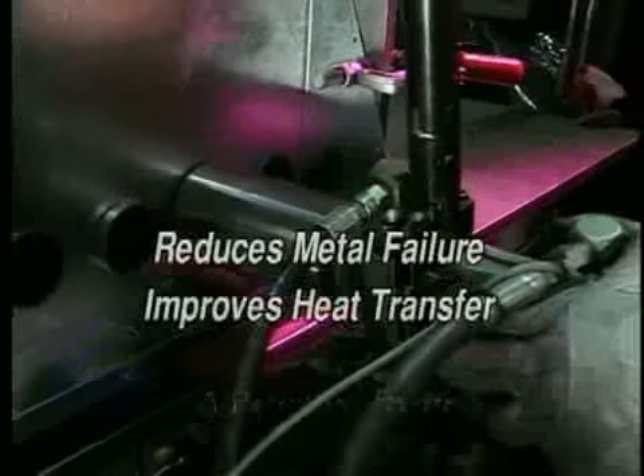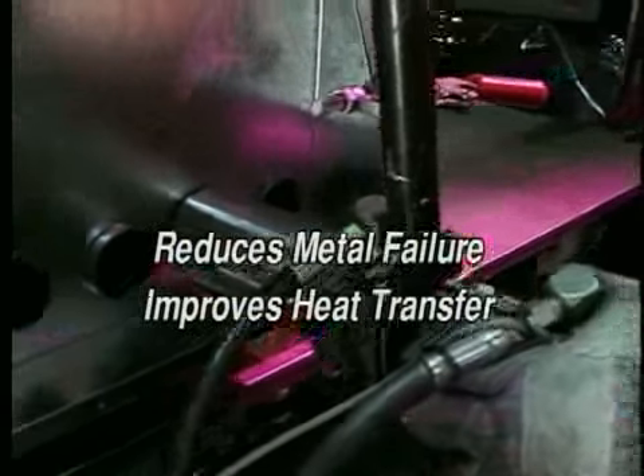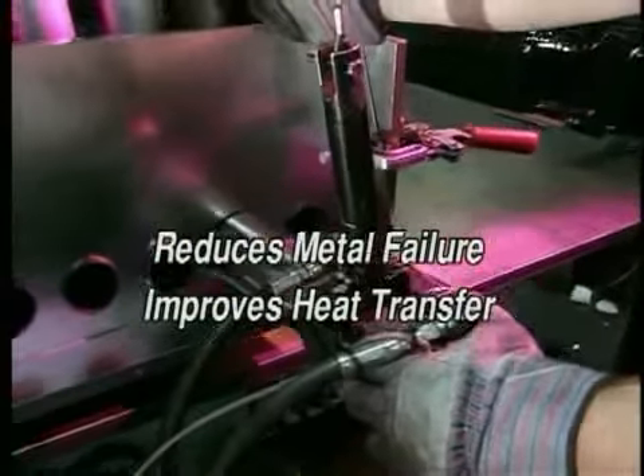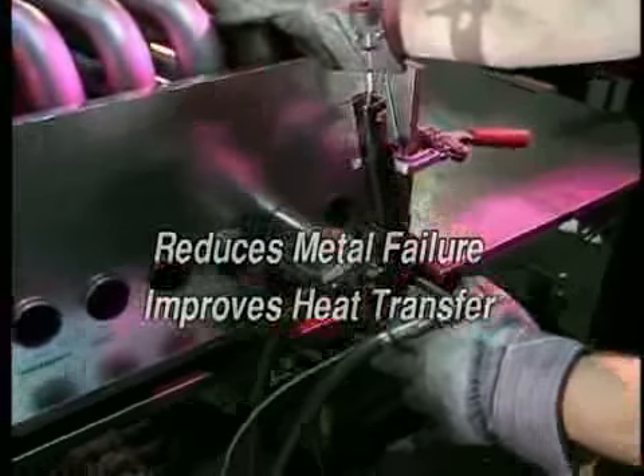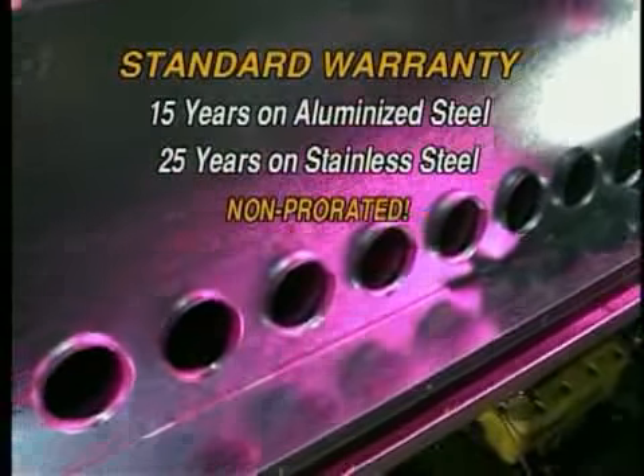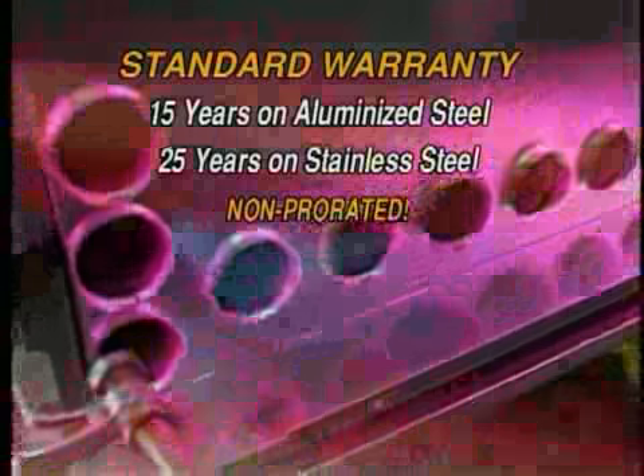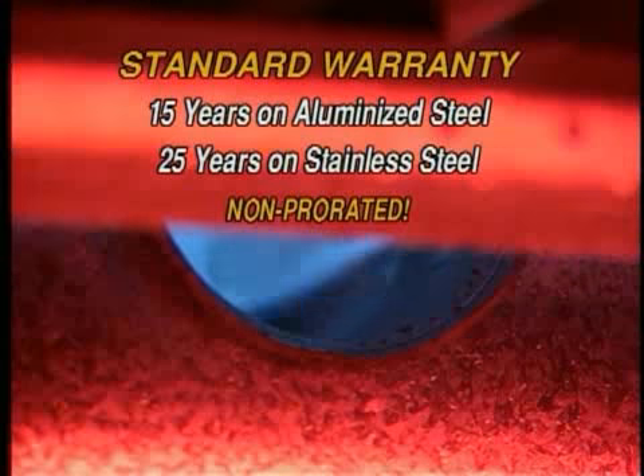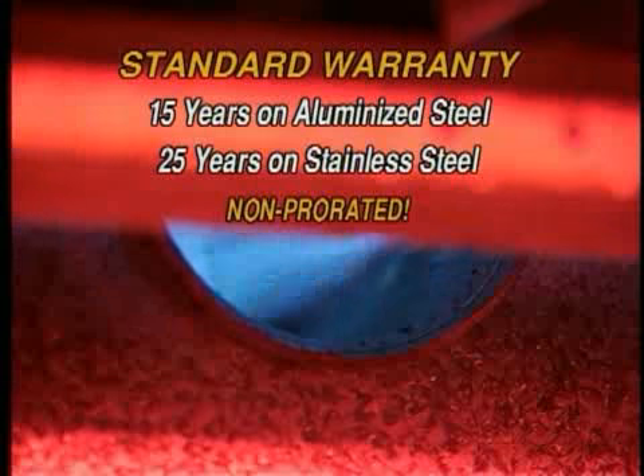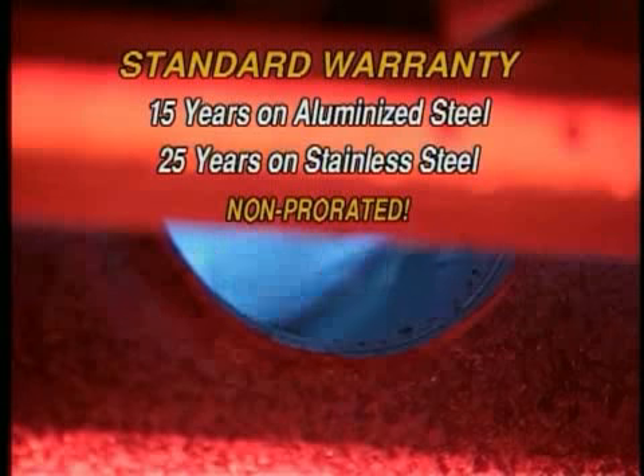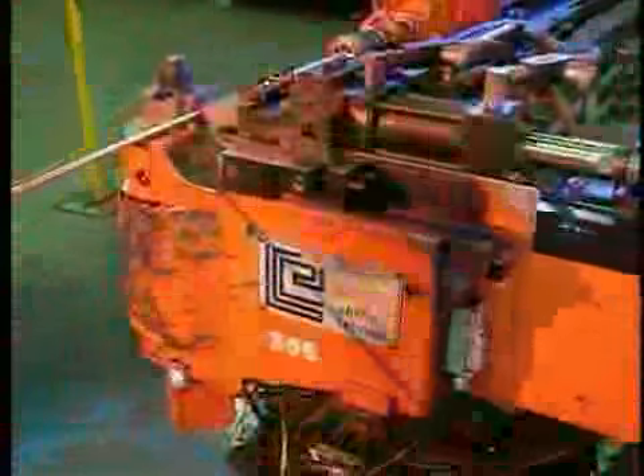Then, the heat exchanger is attached through an expanded metal process that eliminates welding and reduces related metal failures. That sounds pretty good. Well, it works so good, they've extended their standard warranties. 15 years on the standard aluminized steel and 25 on the stainless steel. And it's not a pro-rated warranty. I'm impressed. What else have they done?